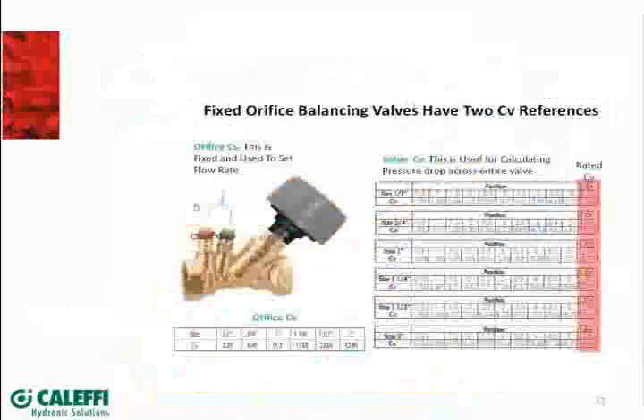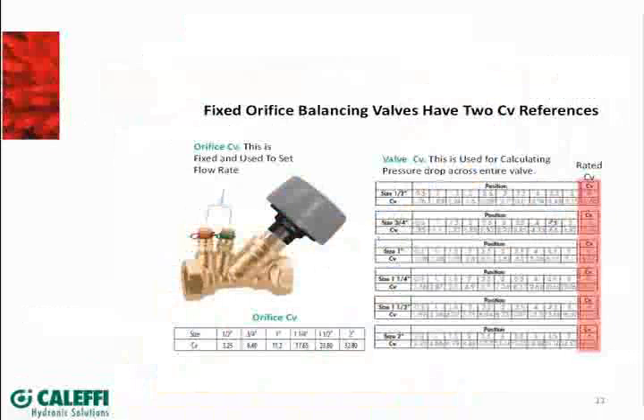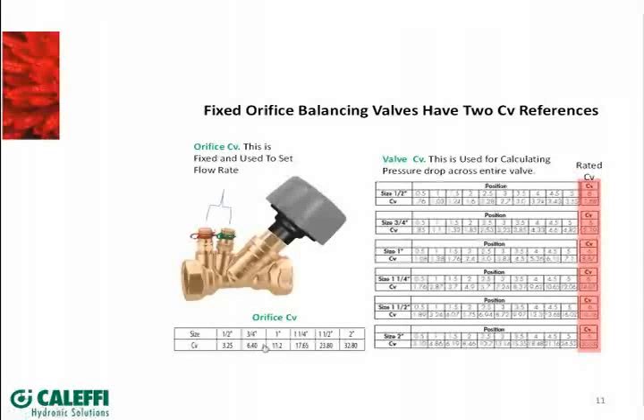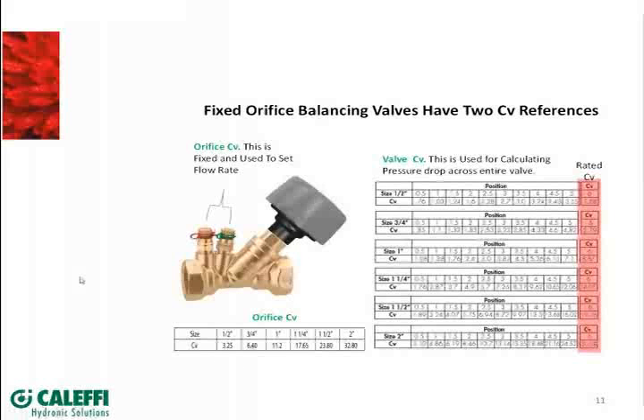Now on this type of valve, this chart comes with it. Let's select a three-quarter size. On the full open position — position number six at the top of the knob — that valve would have a CV of 5.19. That's the pressure drop across the entire valve in the full open position. Over here as we start making adjustments and read across the two ports with a differential meter, going down the three-quarter valve, the CV as read across those ports is 6.40.